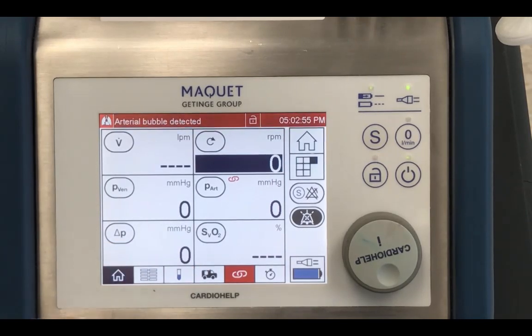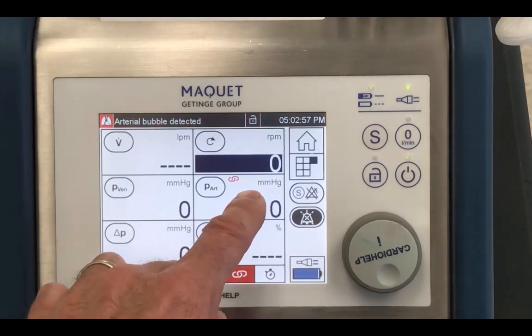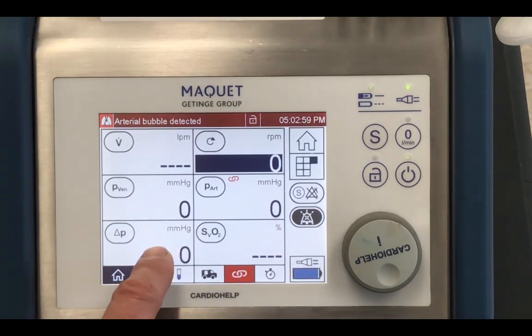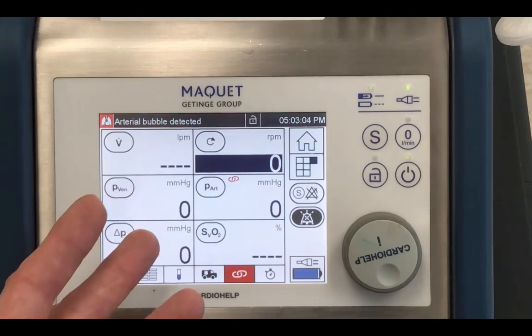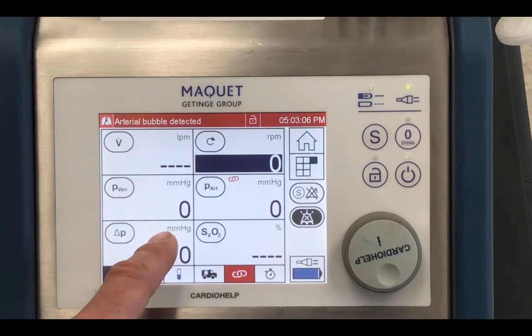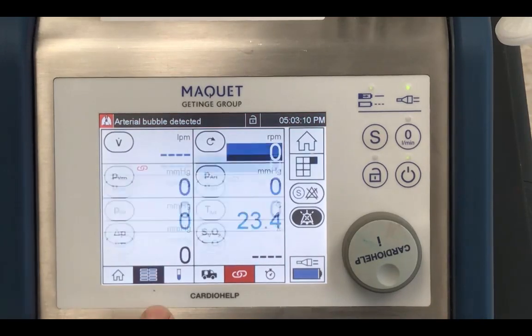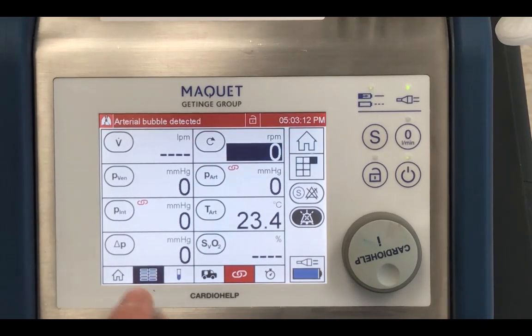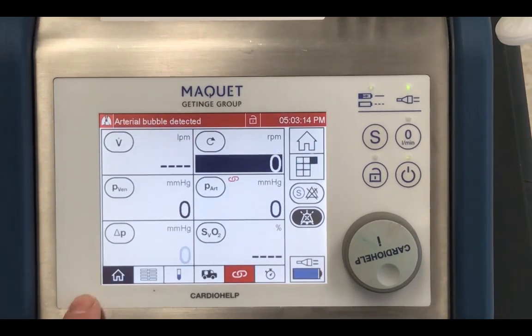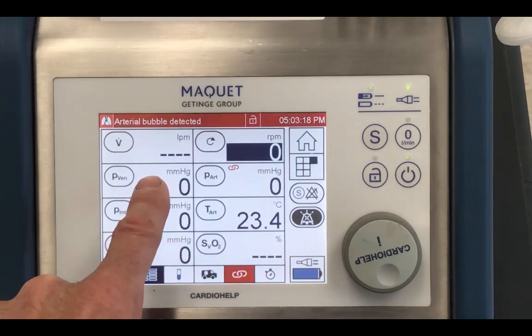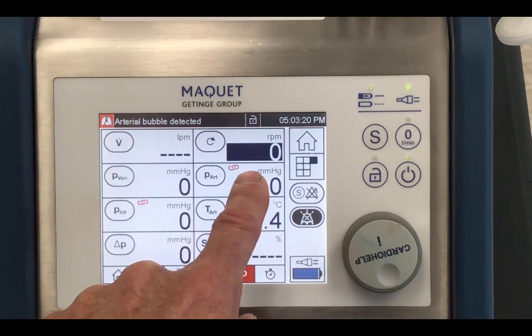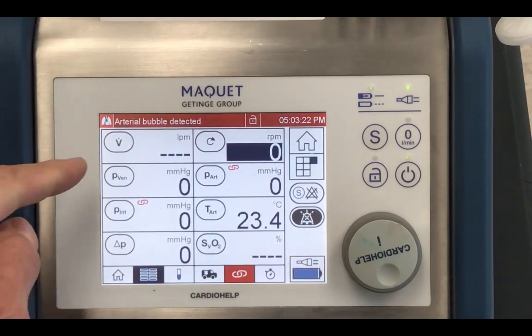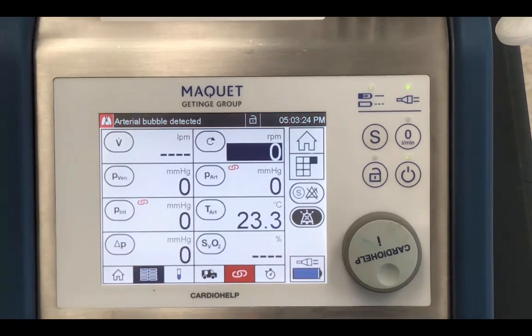The home screen, you should note, shows venous line pressure, arterial pressure, and delta P. This is a calculated number. It's not the third pressure. It's the calculated difference between the P arterial and the P internal. No P internal on this screen. P internal is on that screen. So when you're setting this up and you want to zero your transducers, you have to leave the home screen to get the venous, the internal, and the arterial. Or in other words, the venous, the pre-membrane pressure, and the post-membrane pressure.